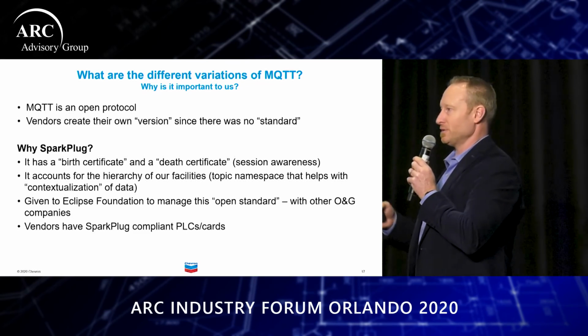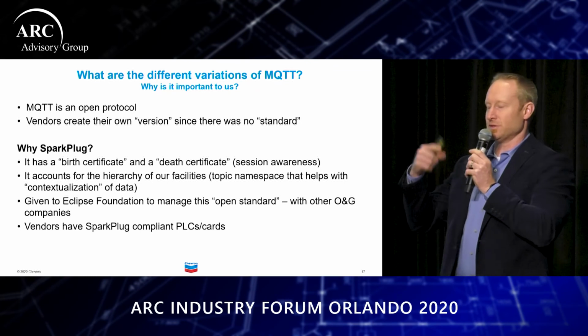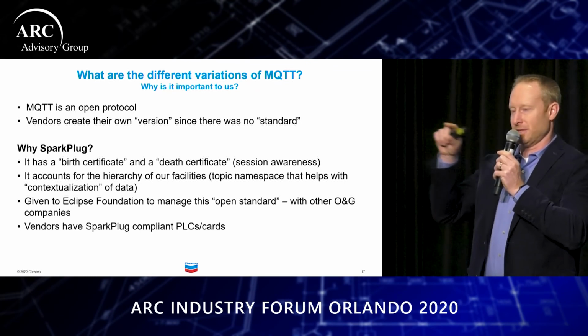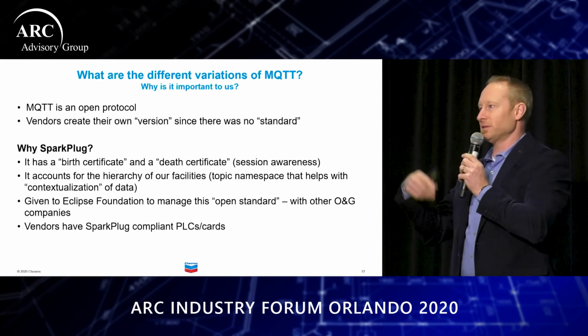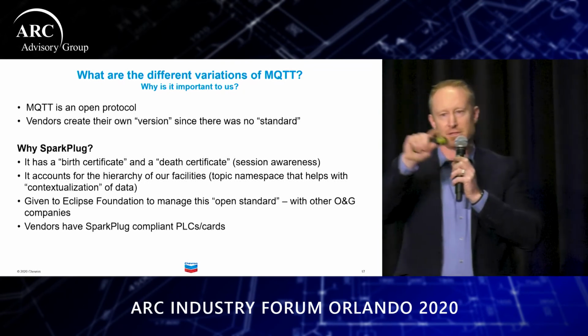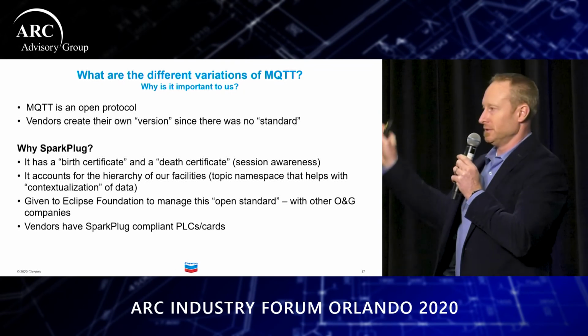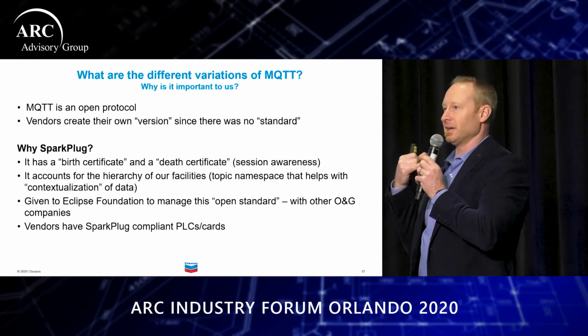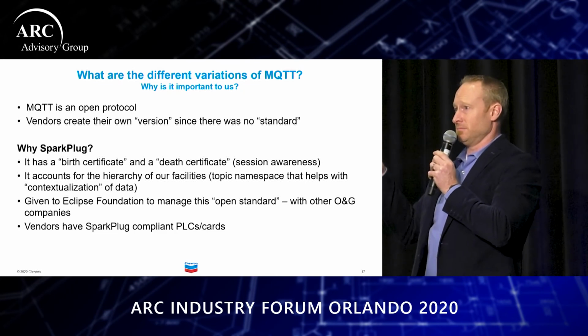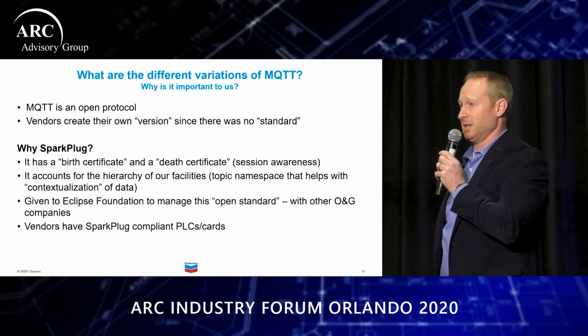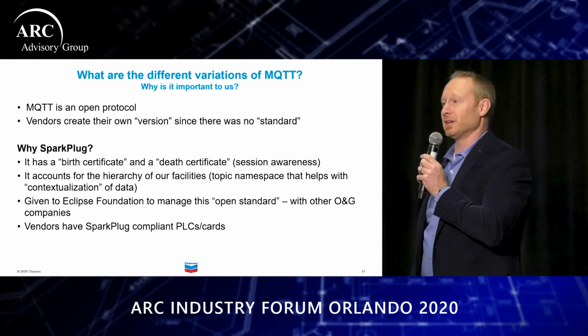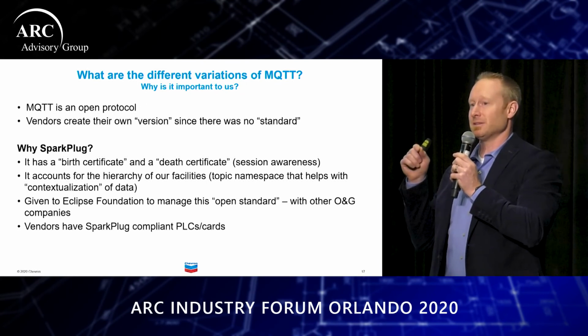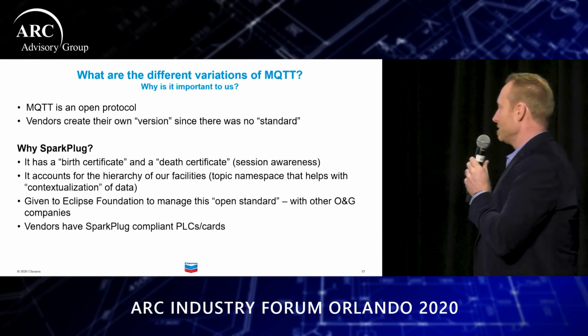I've been part of situations where the operator screens just had the tank level on them. They'd look at the screens several times a day—oh, it's at 10 feet, we're fine—until the next day they get a call saying, hey, you've got liquid running down the tank, because we weren't actually connected to the PLC. So that session awareness is vitally important.